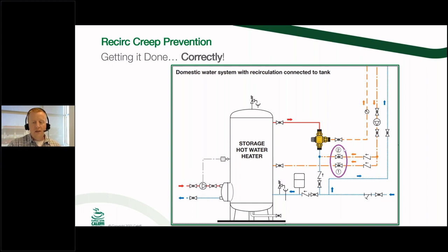Now, these are going to be control valves. I'm going to highly recommend using globe valves in this scenario. However, any valve is better than no valve. But just remember, globe valves are a good control valve, versus a ball valve or a gate valve that's really just meant more for shut-off type applications. But with these valves here, what you're essentially going to be doing is overriding the control that the mixing valve has during times of no demand.